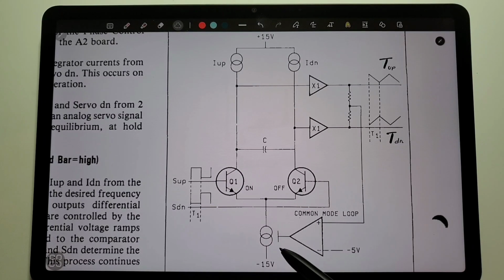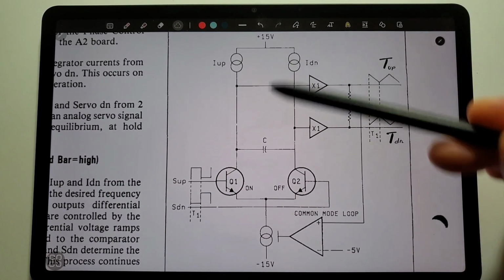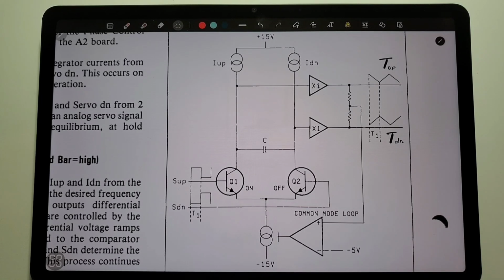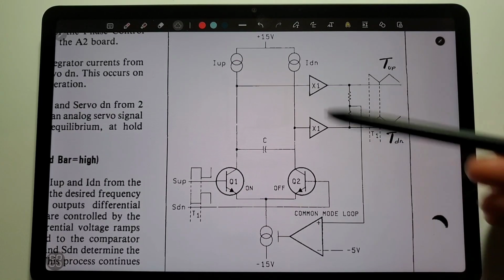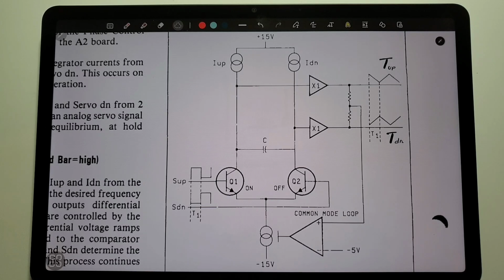Adjusting this current on the tail here controls the overall gain and the overall offset voltage of this differential integrator, so that it can be kept steady with respect to this fixed reference voltage here, maintaining a certain offset level, and keeping the voltage oscillation in the middle of the top and bottom voltage supply rails. Although here they're only showing ×1 or unity, there is a ×10 mode as well, which can also change that offset voltage for certain modes.